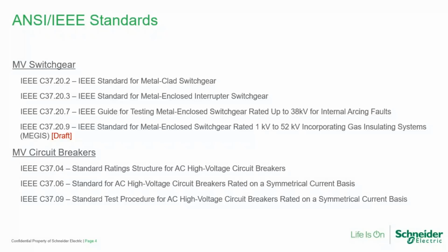Other important switchgear standards I think we need to mention are the C37.20.7, which is the IEEE guide for testing metal enclosed switchgear rated up to 38 kV for internal arcing faults, also known as arc resistant testing. And when you hear a manufacturer state that their switchgear is arc resistant, what they're saying is they have tested their switchgear according to this standard, and that it has passed to some degree, and they should be able to tell you the type of test that they passed according to this C37.20.7.